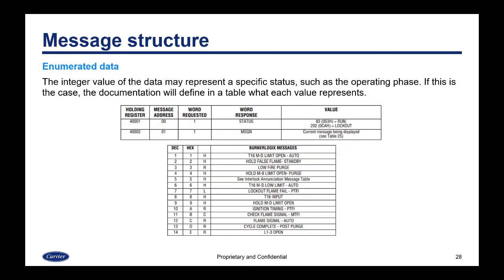Then there is enumerated data, which is very common. The integer value of the data may represent a specific status such as the operating phase. If this is the case, the documentation will define in a table what each value represents. In the example shown, the first register shows the status, and the table below shows what each value represents as a status for a BurnerLogix message.